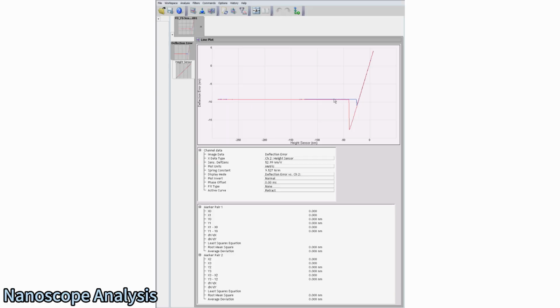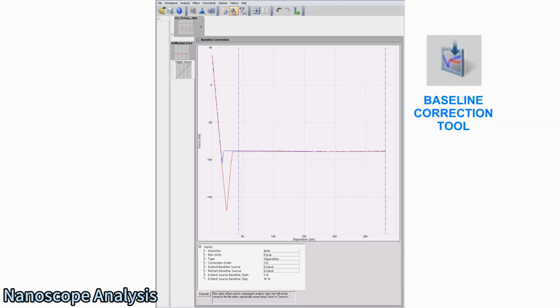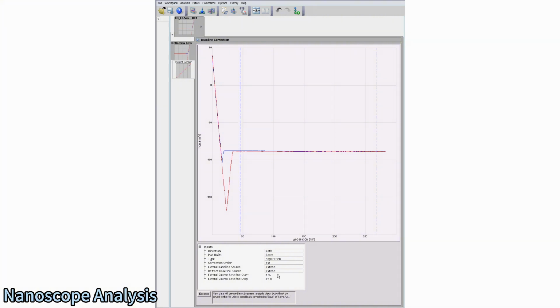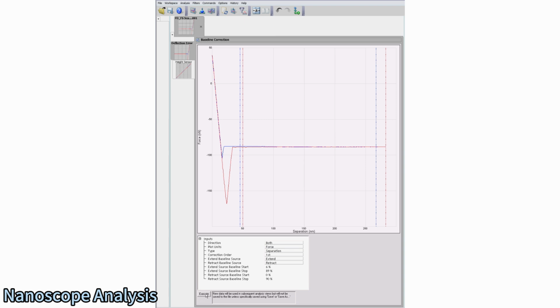Force curve files can be opened for offline review or processing. The baseline correction operation can adjust the original measurement offset or tilt. Use the movable cursors to select the desired section of the curve for correction, choose the data plot options, and then execute the operation to force the curve to the zero reference value.